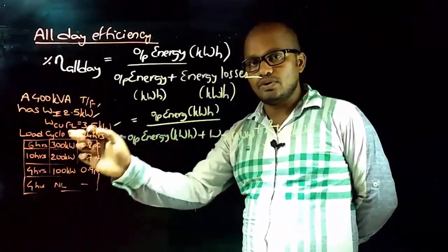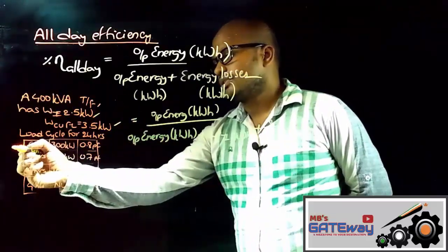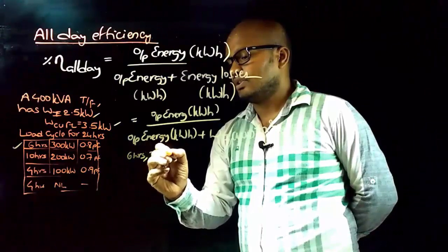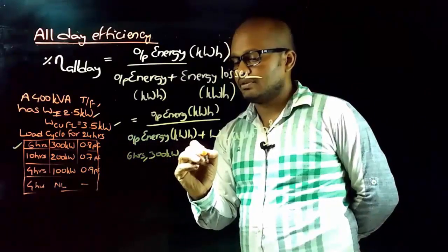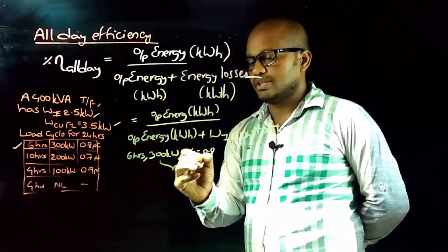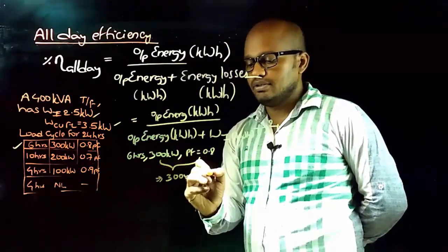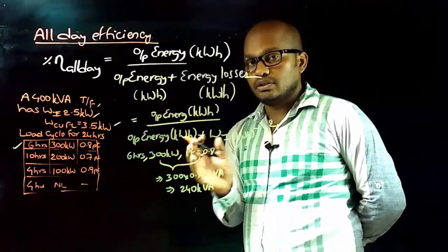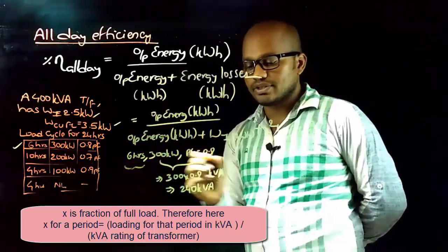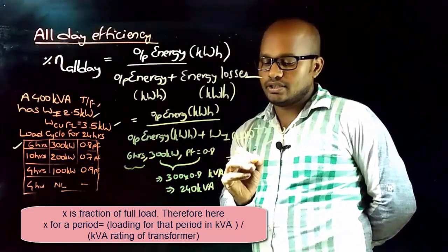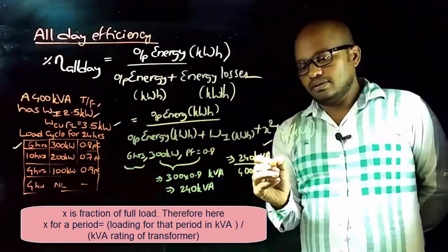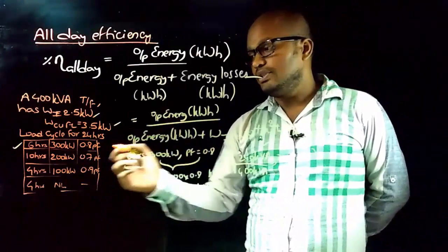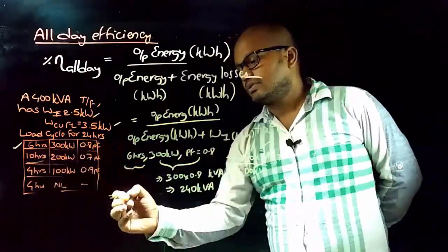Consider the first row: 6 hours at 300 kilowatts with a power factor of 0.8. Multiplying gives 300 multiplied by 0.8, which equals 240 kVA. Therefore, the loading on the transformer for these 6 hours is 240 kVA divided by the transformer rating, giving x equal to 0.6.